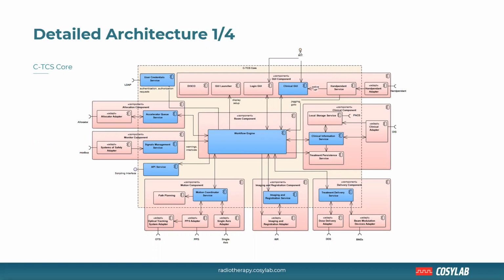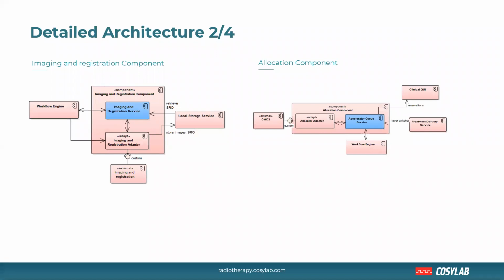And then if you zoom in a little bit more, you would see additional components within those ones in TCS. For example, here's the allocation component. This one is responsible for allocating the beam in a multi-room facility. If you have more than one treatment room, if you have 2, 3, or 4 treatment rooms, you typically still have just one particle accelerator. So you want to be able to schedule the beam, or reserve the beam, and allocate it to the room that is currently in use. So there's only one room that can use it at a time. The allocation component will make sure that the correct room gets the beam, and others have to wait. But they are typically still preparing the patient, or moving the patient out of the room.